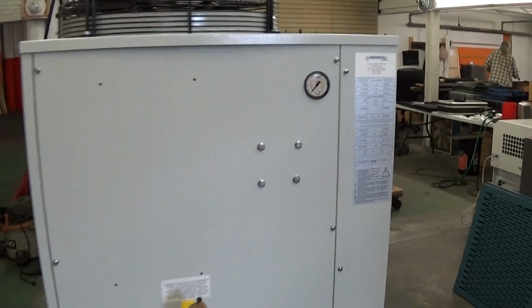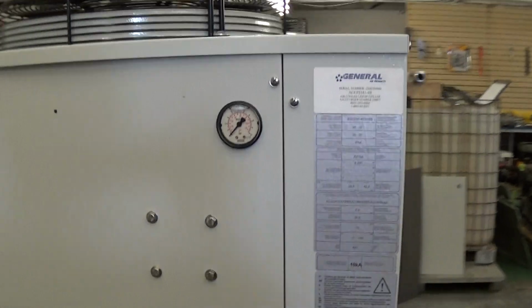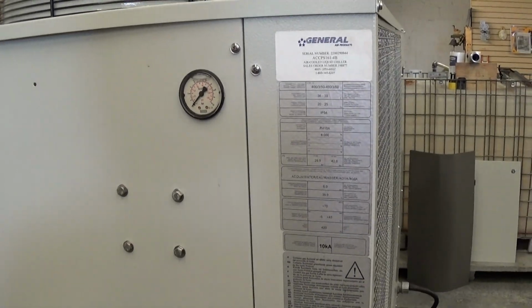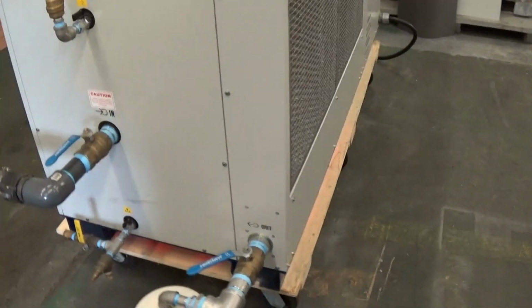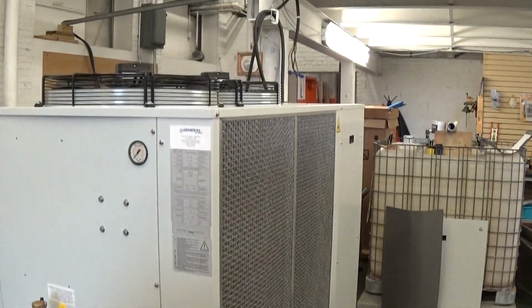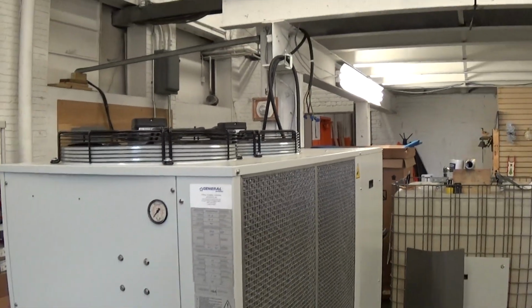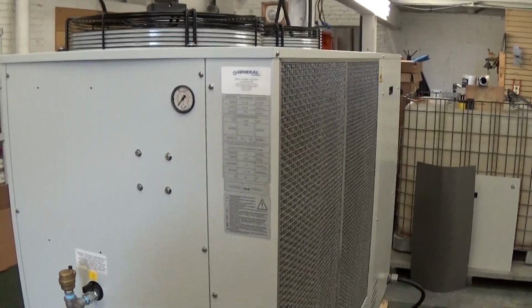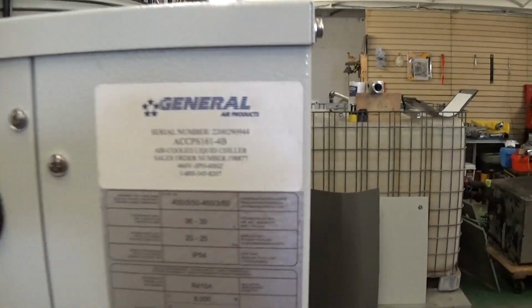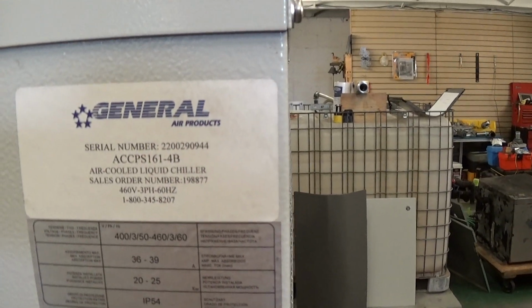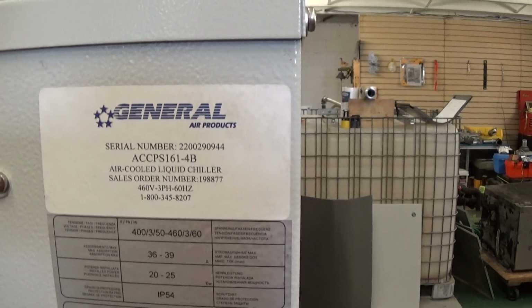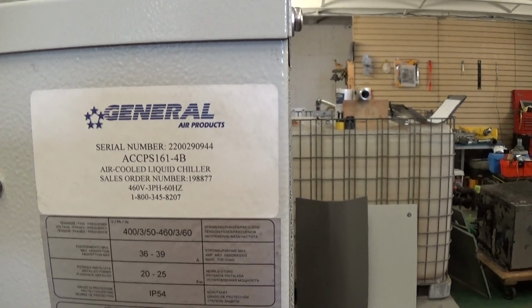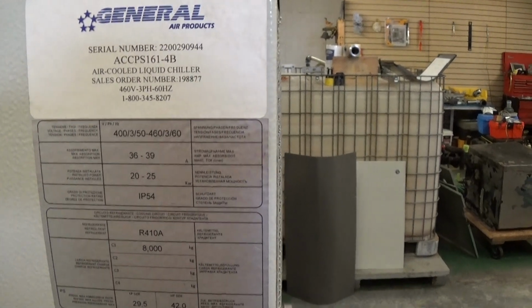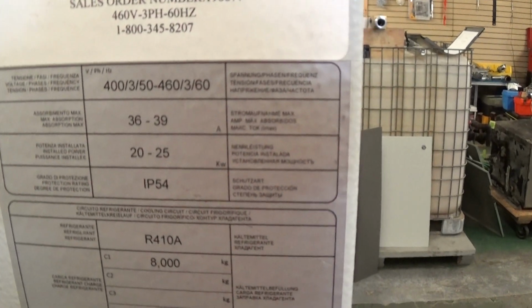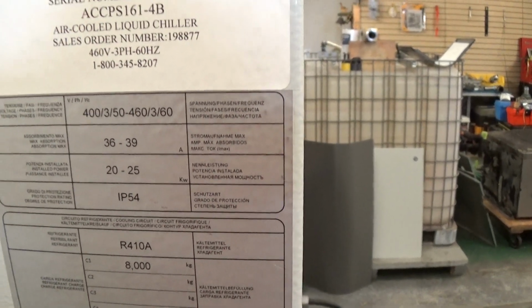We obtained this through some type of lab, actually out here in the Northeast, New England. My point being, it's an outdoor rated unit, but in this case, the prior owner ran it indoors. It is in very, very, very good condition. Model number ACCPS 161-4B. It's 460 volt, 3-phase power. Draws about 36 to 39 amps if you look at the ID tag there carefully.